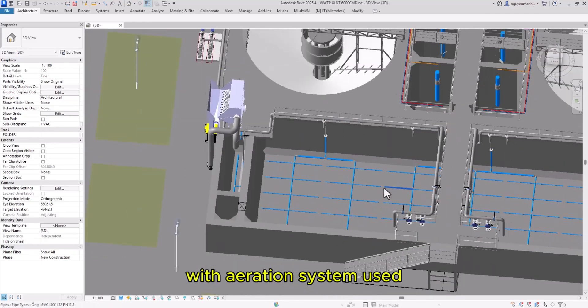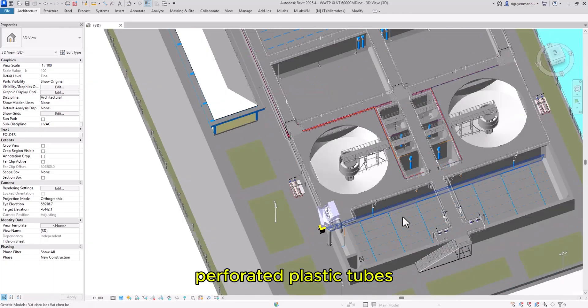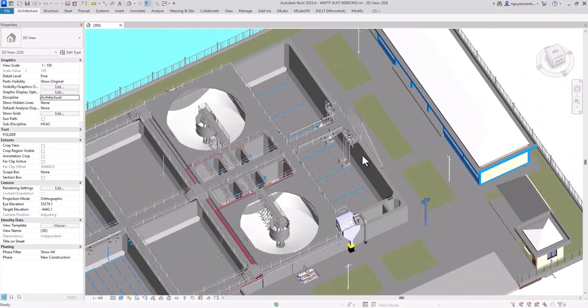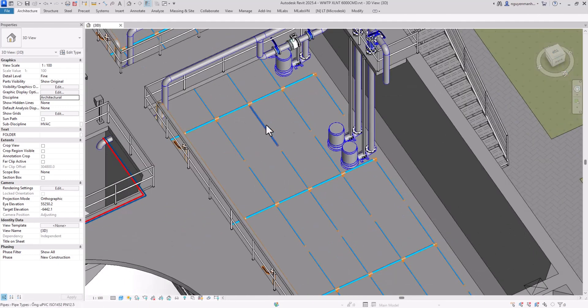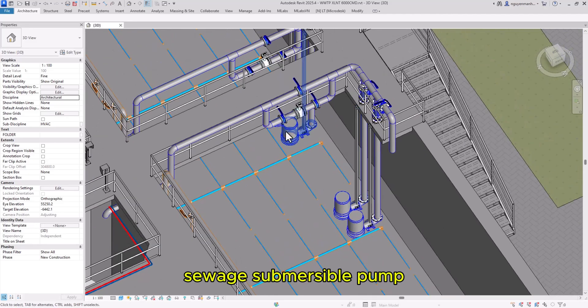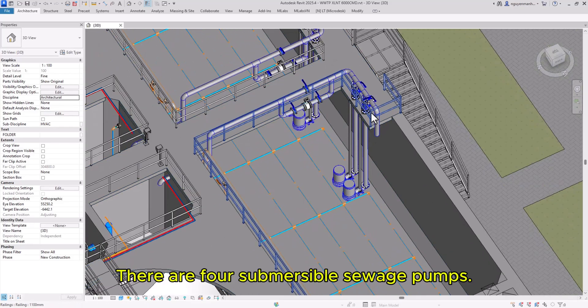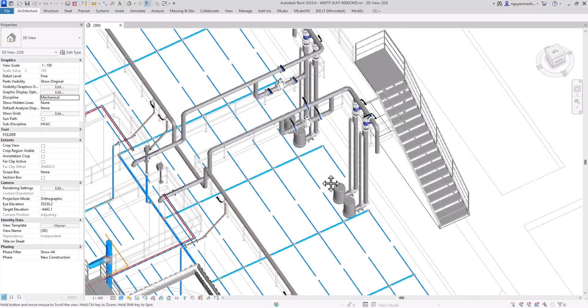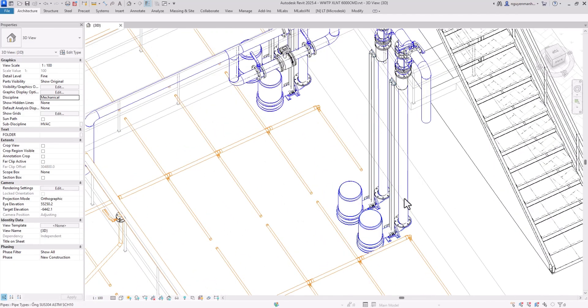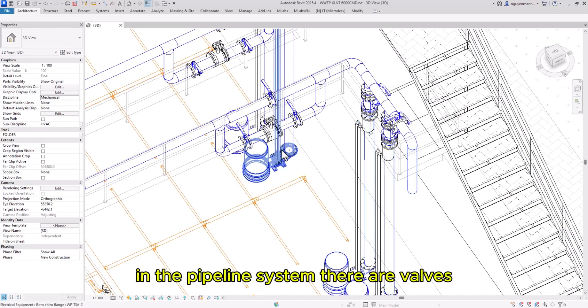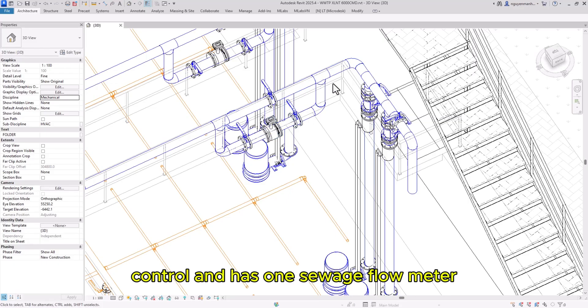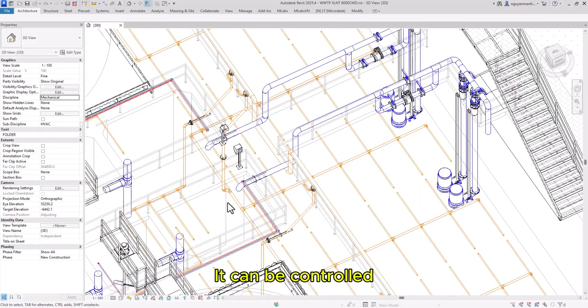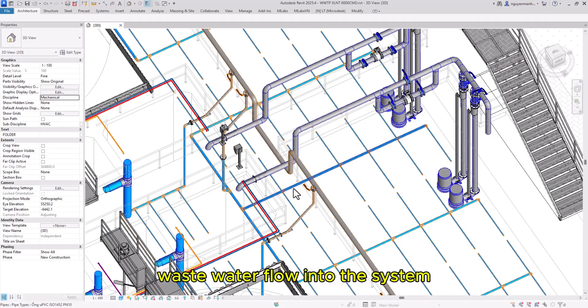The equalization tank uses an aeration system with perforated plastic tubes and perforated air pipe systems. There are four submersible sewage pumps that pump through the pipeline system. The pipeline includes control valves and one sewage flow meter, which helps the operator control wastewater flow into the system.